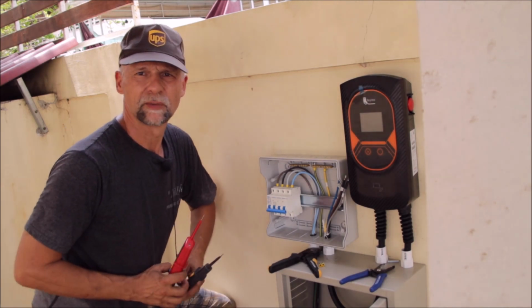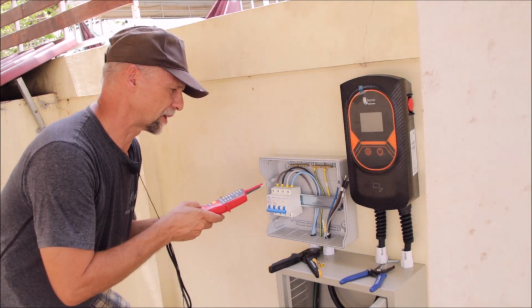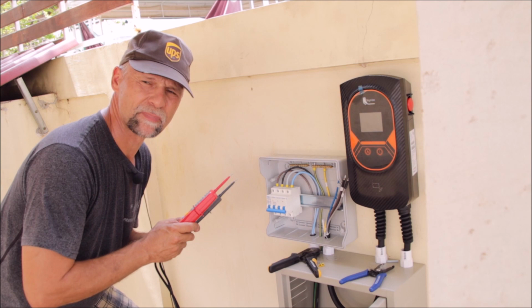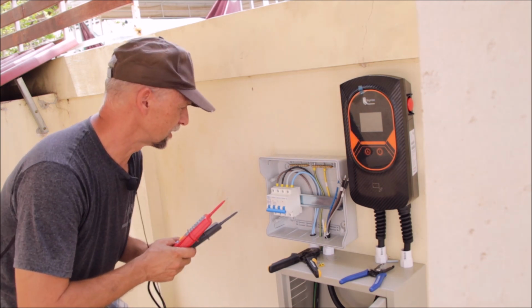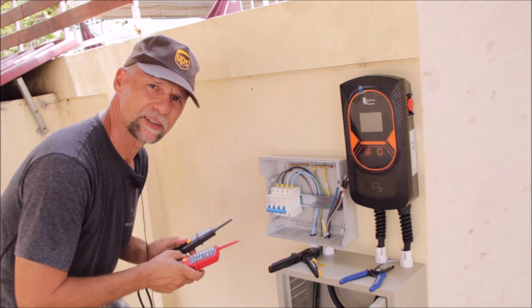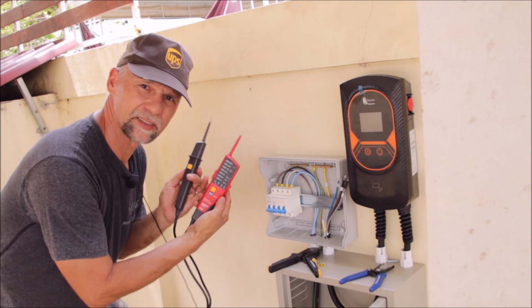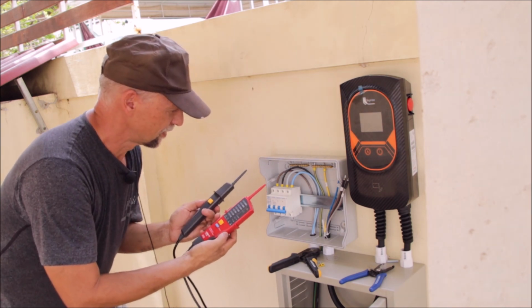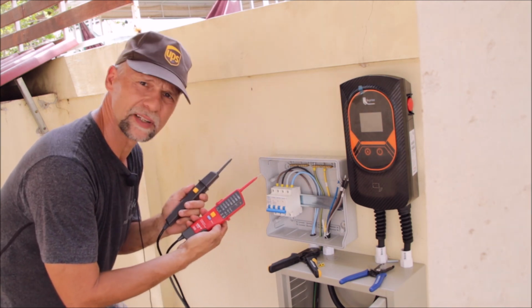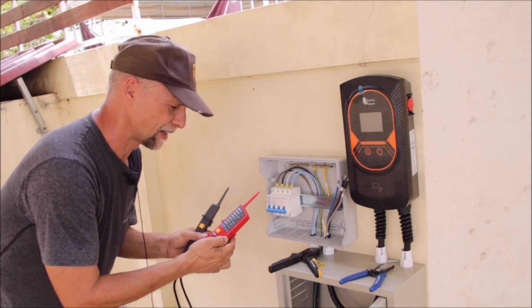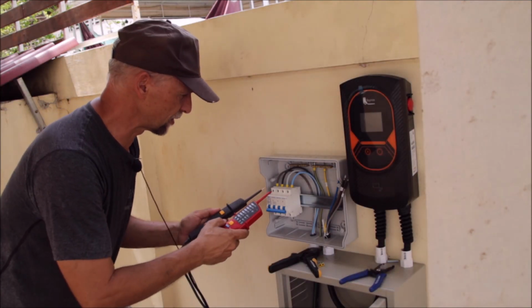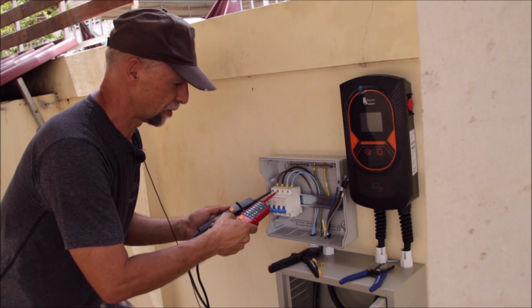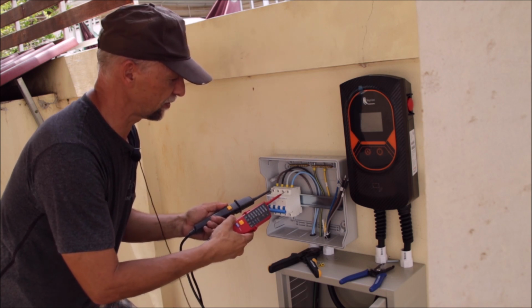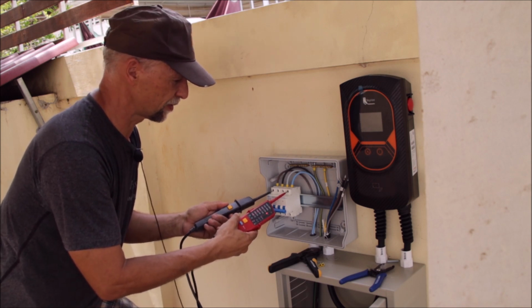MDB is wired up. I have the power already here at my main breaker. So we will talk about the MDB a little bit later, but we can check now if everything is correct. So this is the perfect meter for this. We can check 3 phases very easily, and the meter will not just show us correct voltages, like now 400 volts phase to phase, 230 phase to neutral.